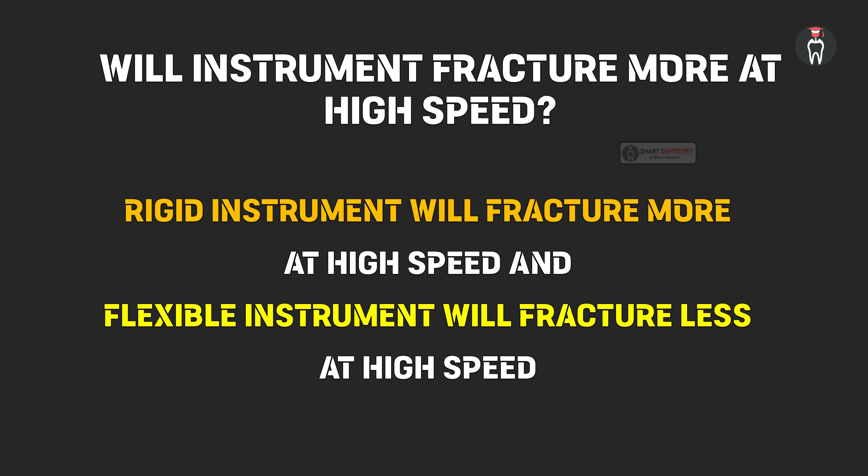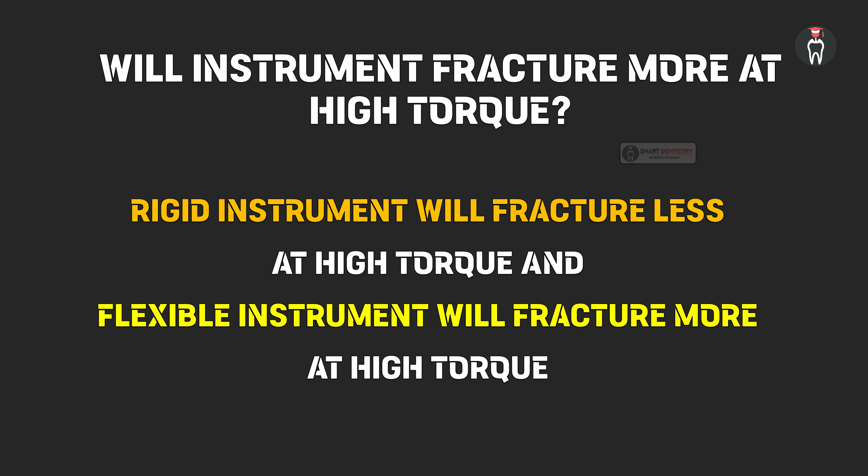Now I will clarify some common doubts. Will the instrument fracture more at high speed? A rigid instrument will fracture more at high speed, while a flexible instrument will fracture less at high speed. Will the instrument fracture more at a higher torque? The rigid instrument will fracture less at higher torque, and a flexible instrument will fracture more at a higher torque.